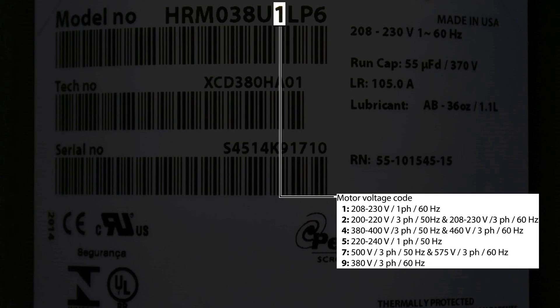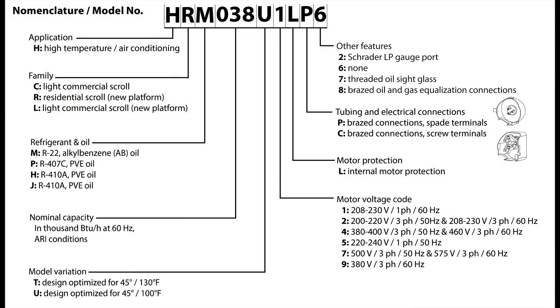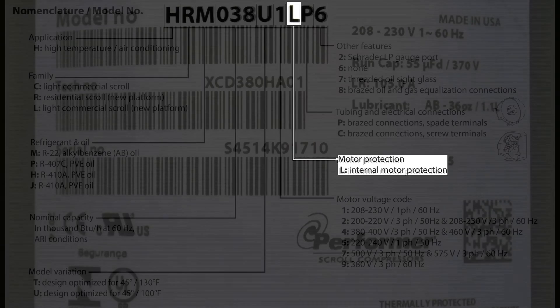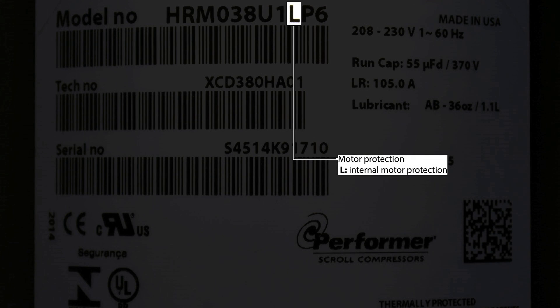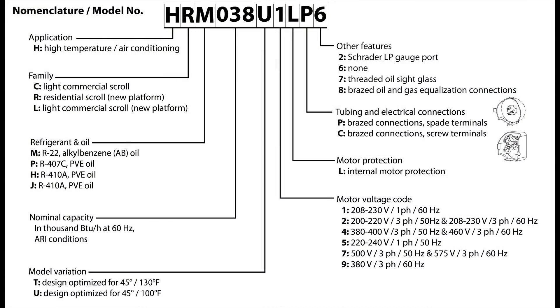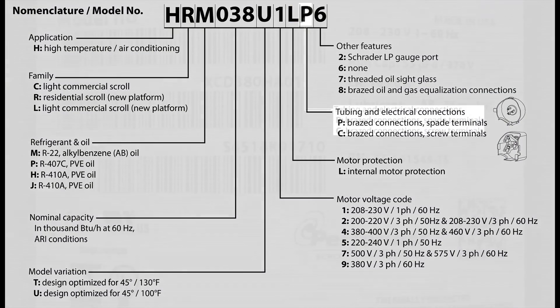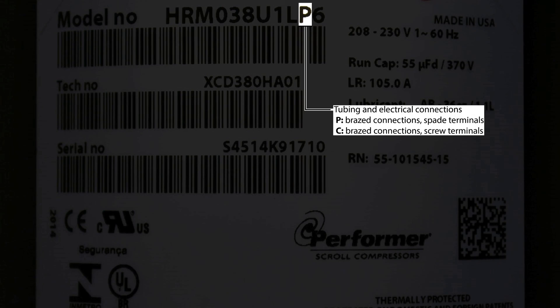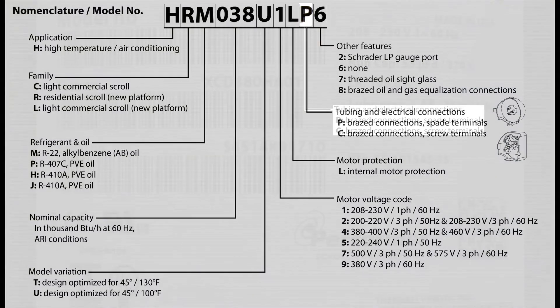The eighth digit in the nomenclature signifies the motor voltage code, denoted by a number which defines the voltage, number of phases, and frequency. The ninth digit specifies the type of motor protection the compressor has, though all compressors in the H-Series have internal motor protection. The tenth digit signifies the tubing and the electrical connections, either a spade terminal or a screw terminal.